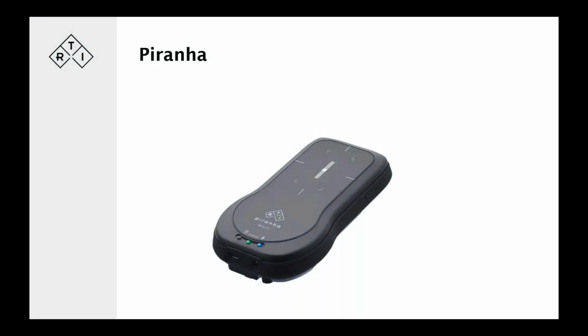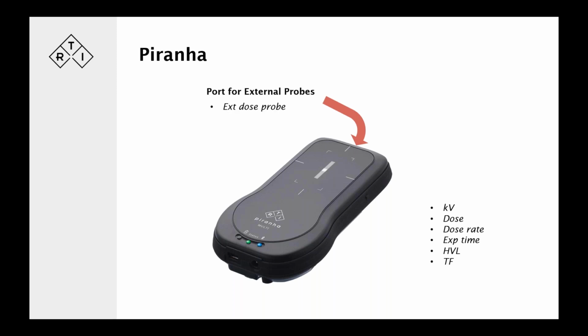So again, looking at the useful hardware, well, Piranha has been around for quite some time, and just again recapping a little bit of what we have. There's a standalone unit with a built-in detector area, where we get the kV, dose rate, exposure time, HVL, and total filtration, all in one shot, based on the radiation captured on that detector area, which is right there. We have a port for external probes, which is on the narrow end. Those external probes can give us dose with the external dose probe, mA and mAs with the mAs probes. The CT ion chamber connects there through the chamber adapter. The light probe also attaches there, as does the CT dose profiler.